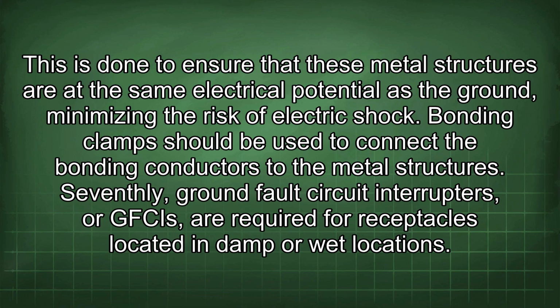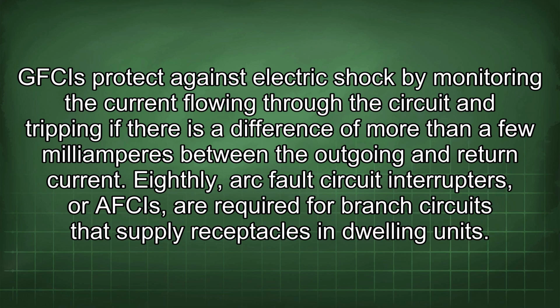Seventhly, ground fault circuit interrupters, or GFCIs, are required for receptacles located in damp or wet locations. GFCIs protect against electric shock by monitoring the current flowing through the circuit and tripping if there is a difference of more than a few milliamperes between the outgoing and return current.